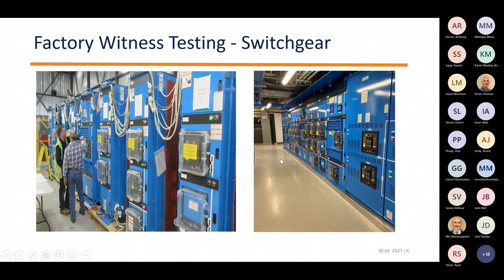There's no going back, so we've got to design and look down the road to get it right. We went to this factory, set it all up, tested the scheme, tested the breakers, and a number of the breakers failed. That's why we're at the factory - we're validating that when it comes into production and we go live, it's going to work. We don't want to lose time in our schedule; time is important. The picture on the right shows the switchgear all together, nicely completed.